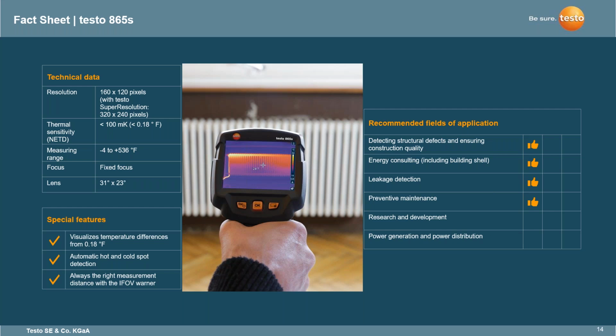So for example, if it could be a 10-degree difference with the IFOV warner on, that 10 degrees could make a big difference in making sure that component is getting closer. For example, like an electrical cabinet, say the connection is loose and it might be picking up something colder behind it as opposed to what you're looking at. You might misdiagnose something, or at least call out that, hey, there could be a potential issue here, there needs to be some action taken. So that is one feature that Testo does have, and by giving you those additional pixels, it makes it a lot more accurate measurement.